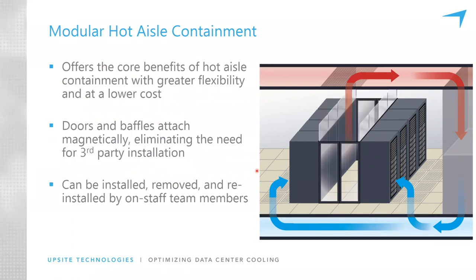This is what it looks like with just baffles, giving that air some emphasis to head in that direction and be sucked up by the return grills. The benefit is that this can easily be installed by site personnel and has a very flexible nature, so that as room conditions change, this can be adjusted very easily. So very beneficial for colo environments.